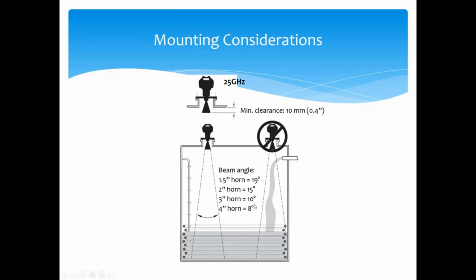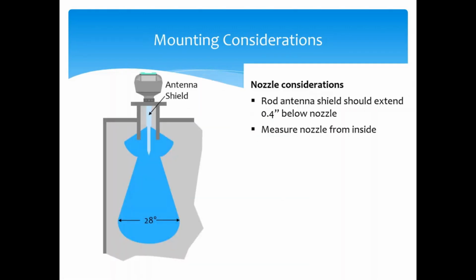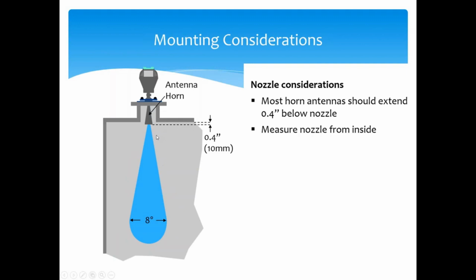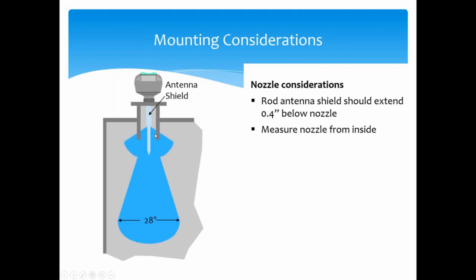Again, same thing with the medium frequency radar. The only thing to show here is that as the horn gets larger, the beam angles become much more narrow, and we'll get down to 6 to 8 degrees in a medium frequency radar. Now, one thing about the nozzle that's extremely critical is that just because the nozzle looks from the outside like it's only 4 or 6 inches in length, that doesn't mean it does not extend inside the tank. So you always want to measure that nozzle from inside the tank, so you know exactly how long it is, and you can make sure your horn or your transducer is extending down below that nozzle.